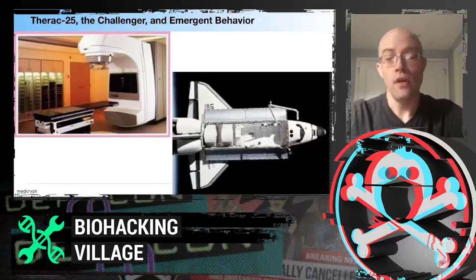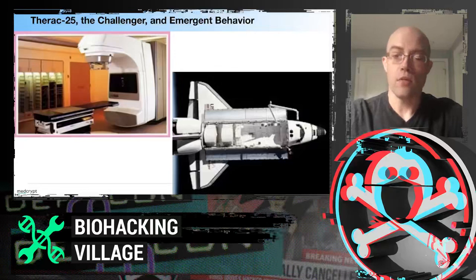And the FDA reviewer says the following: We are in the position of saying that the proposed corrective action plan can reasonably be expected to correct the deficiency for which they were developed. We cannot say that we are reasonably confident about the safety of the entire system to prevent or minimize exposure from other fault conditions. And if I can speak for this FDA employee, I think what they're trying to say...